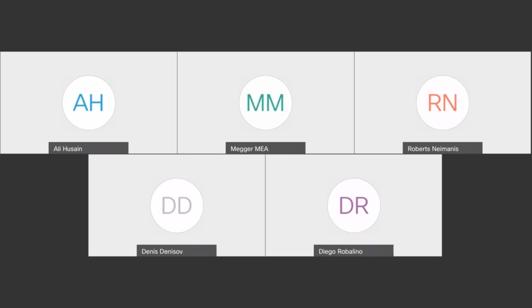This is that yesterday I asked you about the C2 variants acceptance criteria. You told for C1, for the bushings, it will be 5% of the nameplate ratings. For the C2, there is no such limitation, you told, but it should be compared with the other three phases. But is there any idea if the difference is maybe 200% with the nameplate results for the C2? Is it okay, acceptable? All three phases are the same, almost 200%, 210% within this.